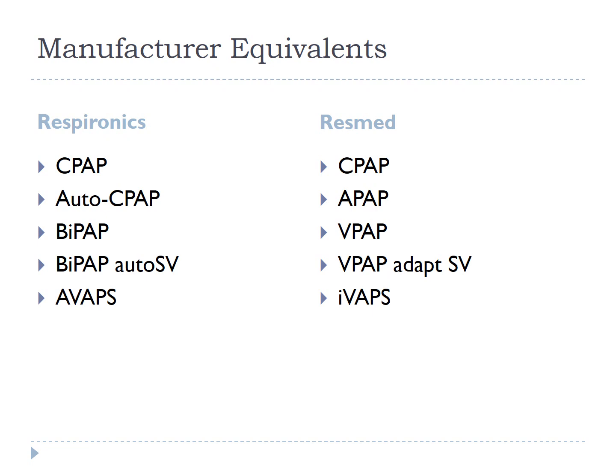Now, when we talk about an auto-titrating device, this is where the machine has a set pressure that it will never go below and a set pressure that it will never go above, but it will adjust pressures in between those two limits in response to the patient's airflow. So the machine's response to a decrease in airflow is to increase pressure to make sure the patient is breathing throughout the night.